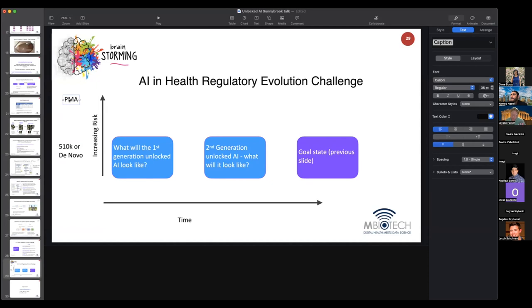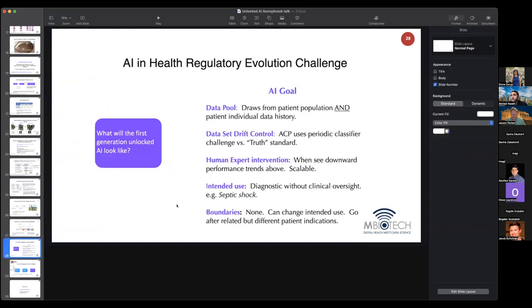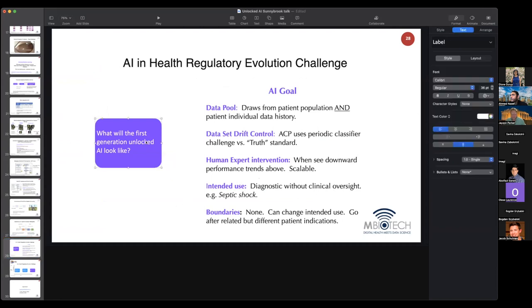The FDA would not feel sufficiently comfortable right now with an unlocked neural network submission just because you submit a PMA. The first system has to be a screening function — it cannot be diagnostic. Whatever we do with unlocked neural networks, it has to be for screening purposes. That poses a commercial challenge because companies and investors generally aren't happy with screening applications since they're not that lucrative.